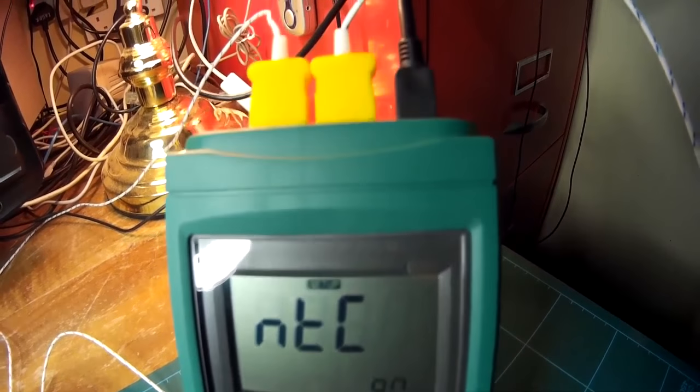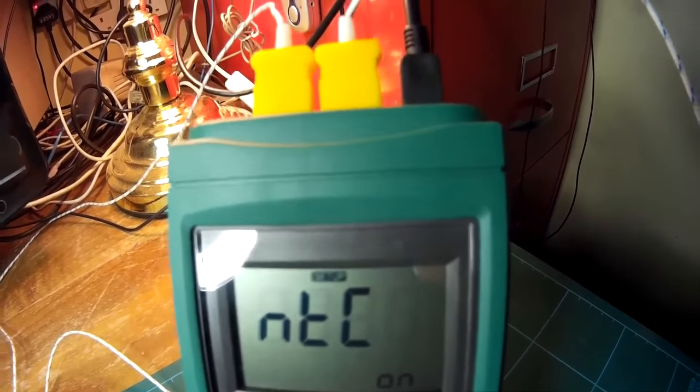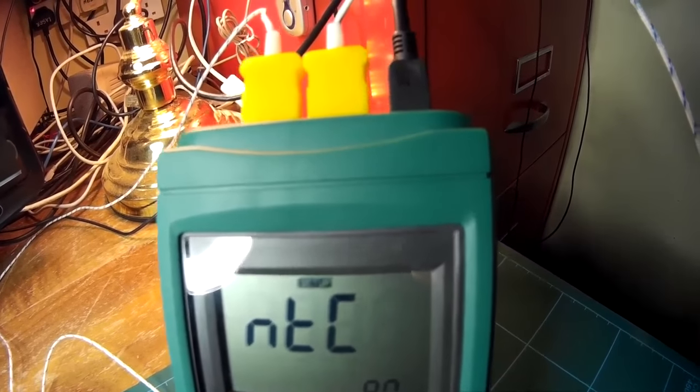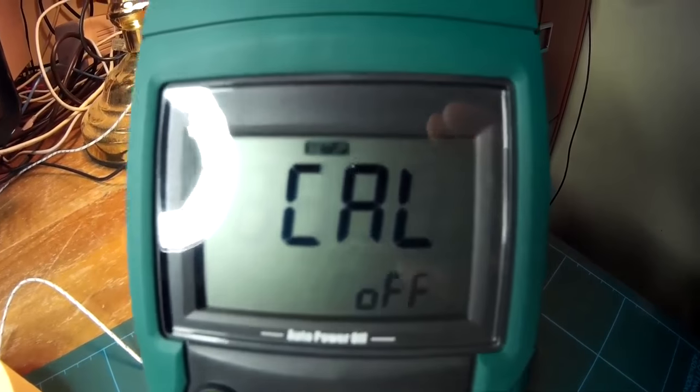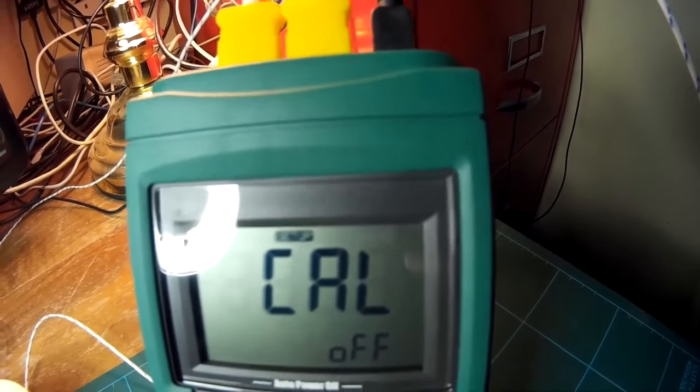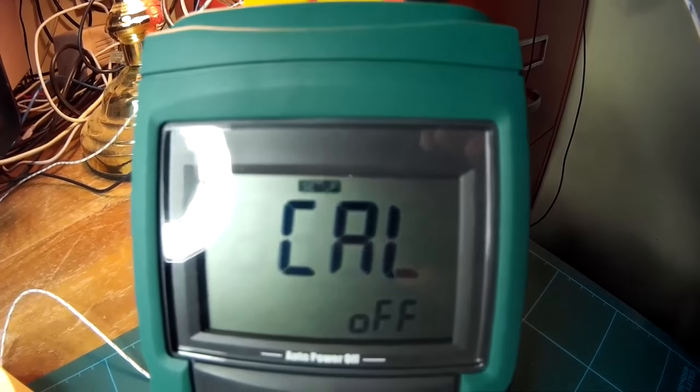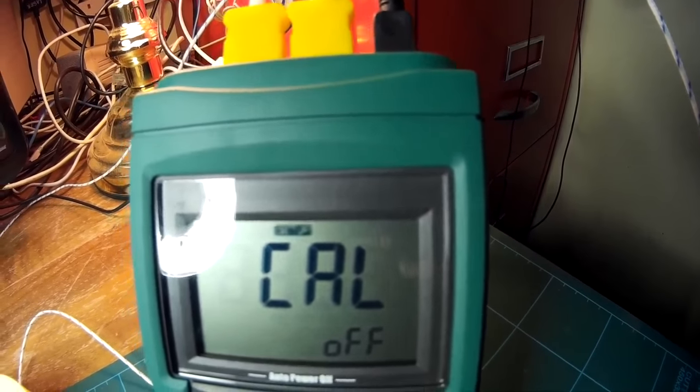OK, NTC I don't know, it's a kind of calibration, automatic calibration. But I don't go to change this. And this is most critical: don't go for CAL ON because this will destroy the calibration of the meter. So be very careful with this.